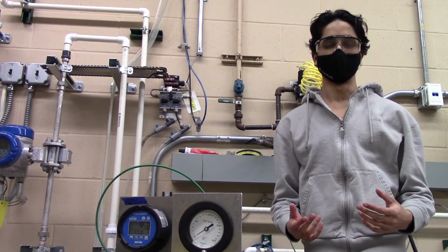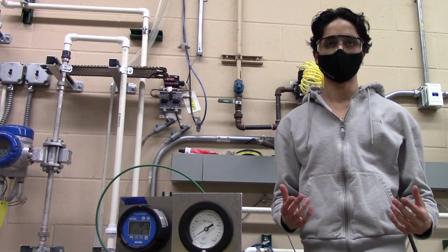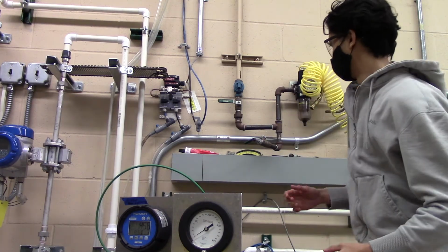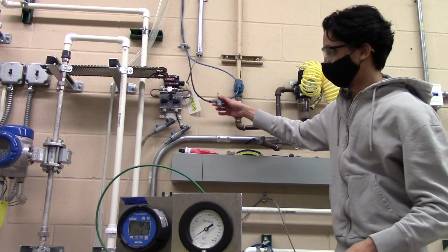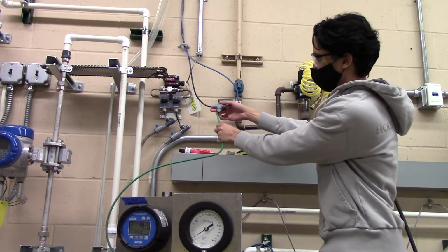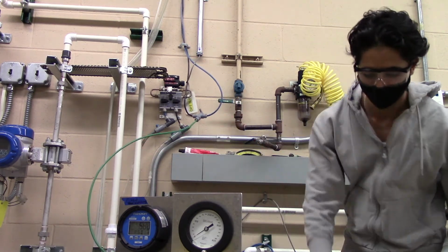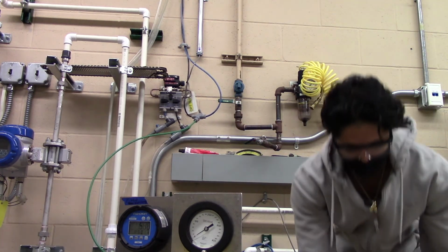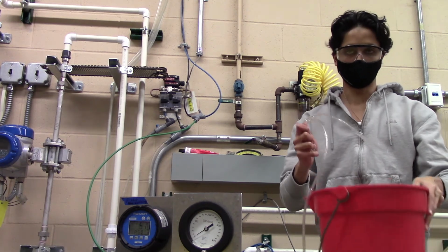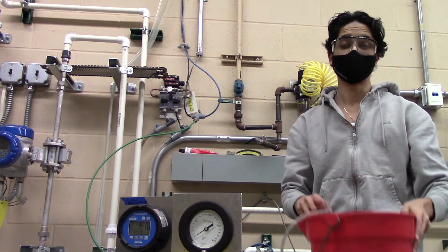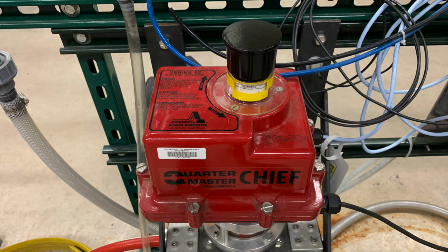When taking the pressure readings for the straight iron loop, as opposed to ones involved in the entire system, you must use the straight iron three-way valve with the same pressure gauge application and procedure, and when bleeding out the valves, make sure the exiting water is flowing into a bucket to avoid water spillage. Continue this process until all pressure readings are measured for each material pipe at each chosen flow rate.